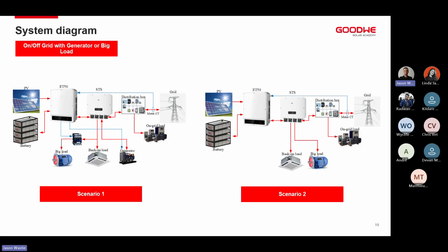If we look at the picture in scenario 1, we have your generator connected to the generator port, and the blue dotted arrow going into the generator is the automatic start-stop functionality. Where it says big load, we've got a second dry contact relay running into an external contactor, and that external contactor allows us to control a secondary output of load, meaning we can have big load mode and backup loads, provided we don't exceed the 55 kilowatts. We can connect that in order.